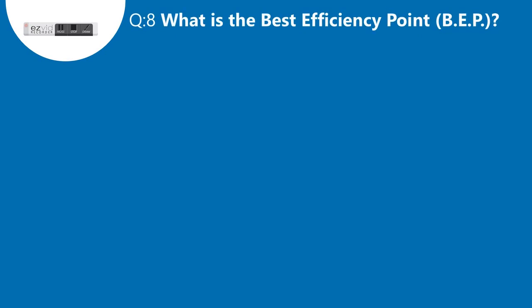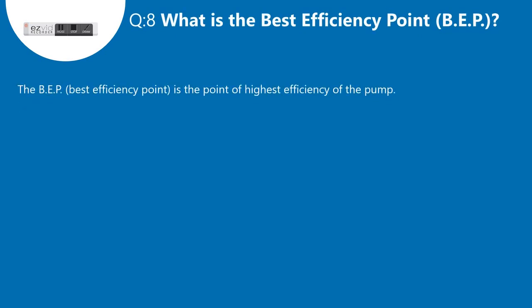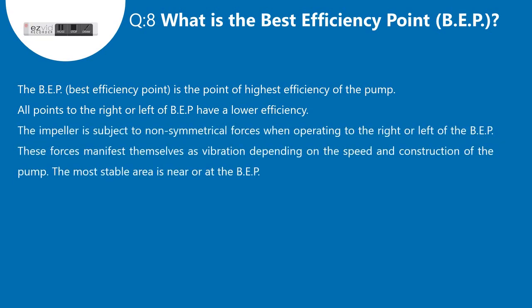Question 8: What is the best efficiency point, BEP? The BEP, or best efficiency point, is the point of highest efficiency of the pump. All points to the right or left of BEP have a lower efficiency. The impeller is subject to non-symmetrical forces when operating to the right or left of the BEP. These forces manifest themselves as vibration depending on the speed and construction of the pump. The most stable area is near or at the BEP.